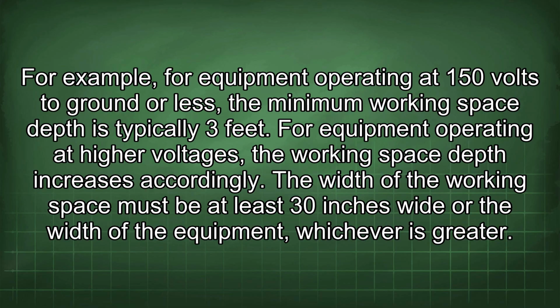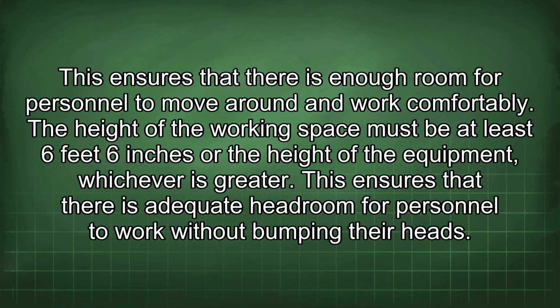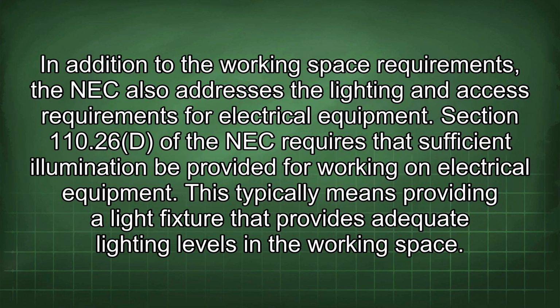The width of the working space must be at least 30 inches wide or the width of the equipment, whichever is greater. This ensures that there is enough room for personnel to move around and work comfortably. The height of the working space must be at least 6 feet 6 inches or the height of the equipment, whichever is greater. This ensures that there is adequate headroom for personnel to work without bumping their heads. In addition to the working space requirements, the NEC also addresses the lighting and access requirements for electrical equipment.